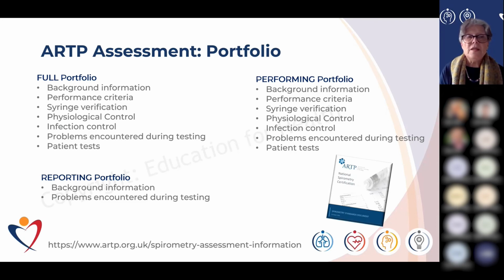So it's a verification procedure. You need to do a physiological control, so that's taking someone with normal lung function, and you would capture that over 10 consecutive days or 10 working days, or that there's always flexibility because you might not be working 10 days. So you might want to do over a 2 or 3 week period, and that's acceptable, that's perfectly okay.